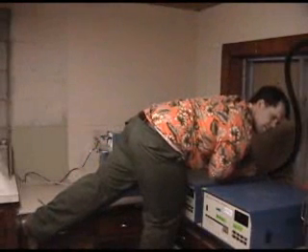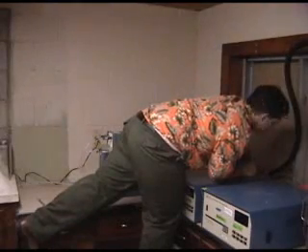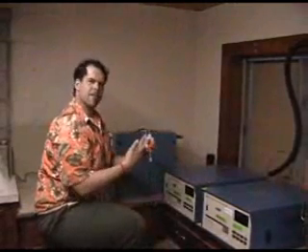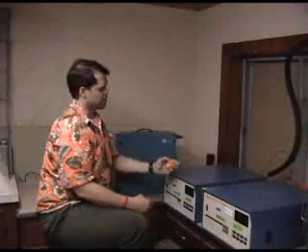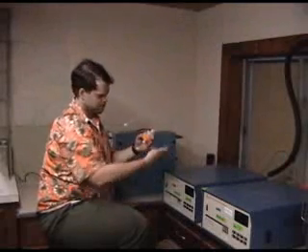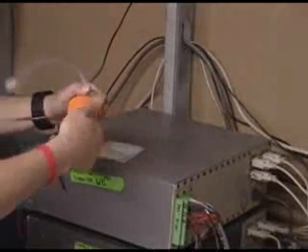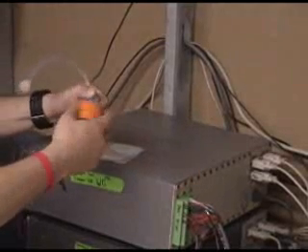Two little screws to undo, and it pops out. Make sure you realize that there's an arrow on this thing showing the direction of airflow. Airflow on this analyzer always goes from the top to bottom, so don't replace it back in this way. This will do you no good. To change the filter, unscrew the top from the bottom.